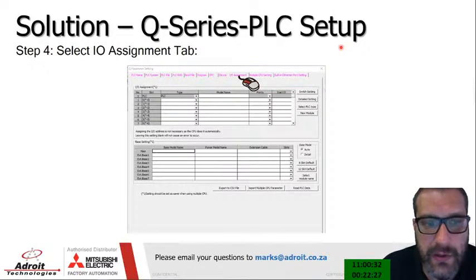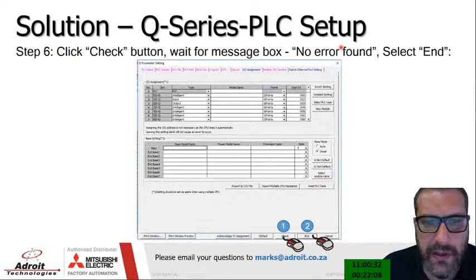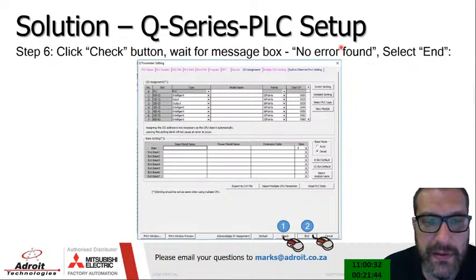Once you open the parameters, you'll get the Q Parameter Settings page. Click on IO Assignment to open it. IO Assignment is where you tell the PLC which cards are in which slots of the rack. I clicked 'Read PLC' which reads all the cards currently installed. You can see there are intelligent cards and some IO cards. Our CC Link card is in slot number six — it's an intelligent card with 32 IO points, and its start XY address is 060. Then you click Check and End.